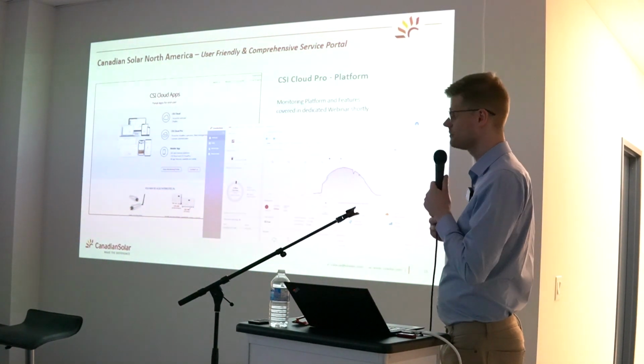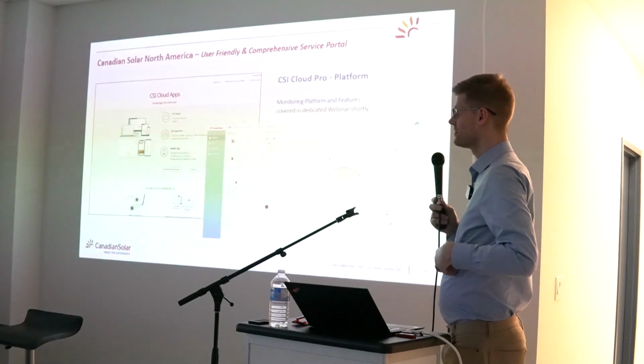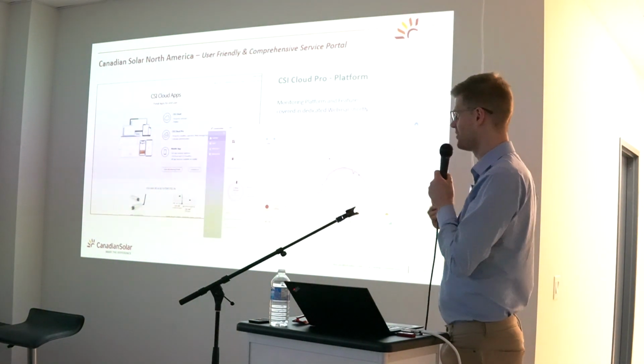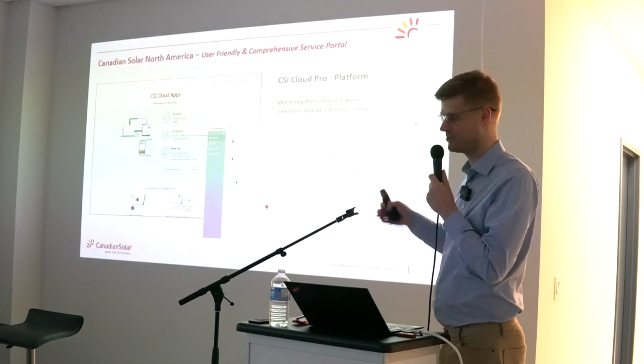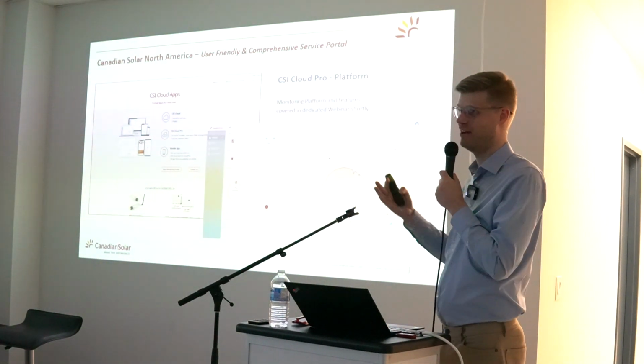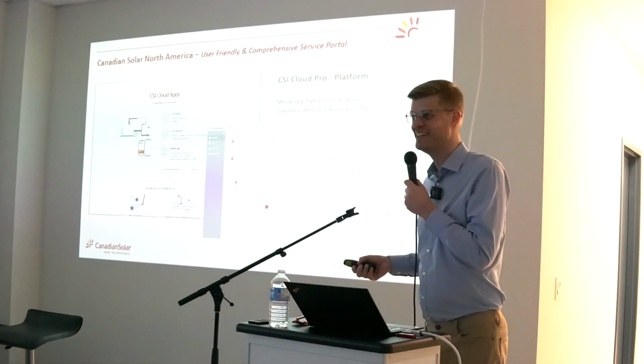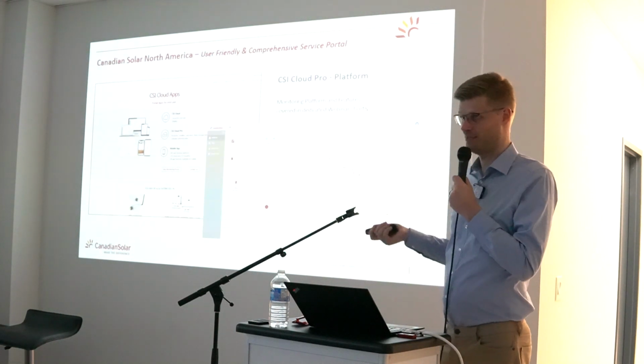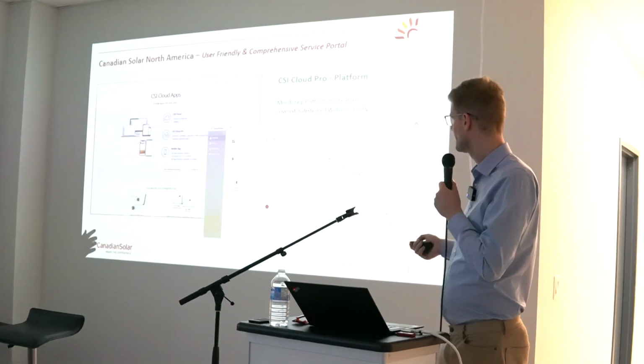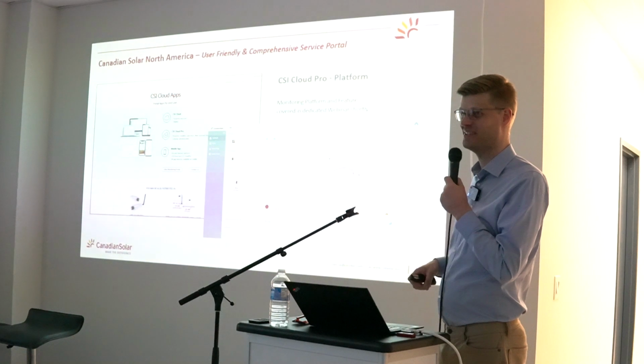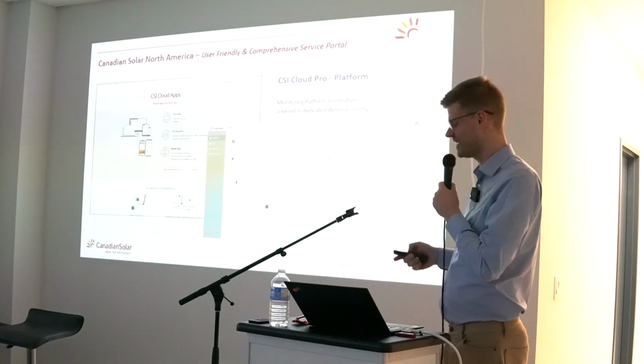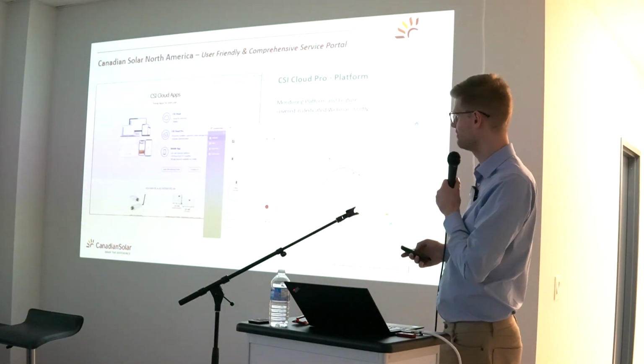And actually what we have is an undersized system, right? Exactly. So we have a 125 kilowatt inverter limited to a certain power class, but we only have probably 8 kilowatts connected to it, because it's just a test system for us. So that's why you'll see only a small curve instead of a big curve of our 60 kilowatt rooftop system we have here in this building.